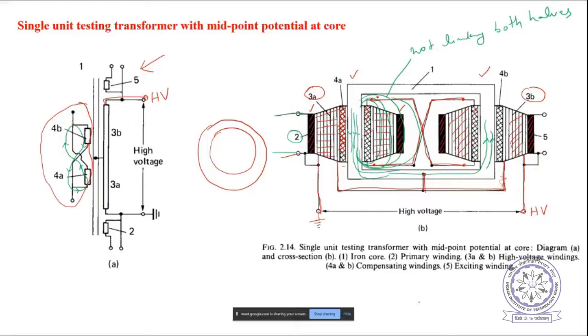So that's the advantage of having two halves and two legs, achieving a single unit testing transformer by making the midpoint of the high voltage winding at core level. This is the highest voltage that can be obtained - the mechanism and design by which the highest voltage can be obtained using single unit transformers. You can ask any questions if you have.